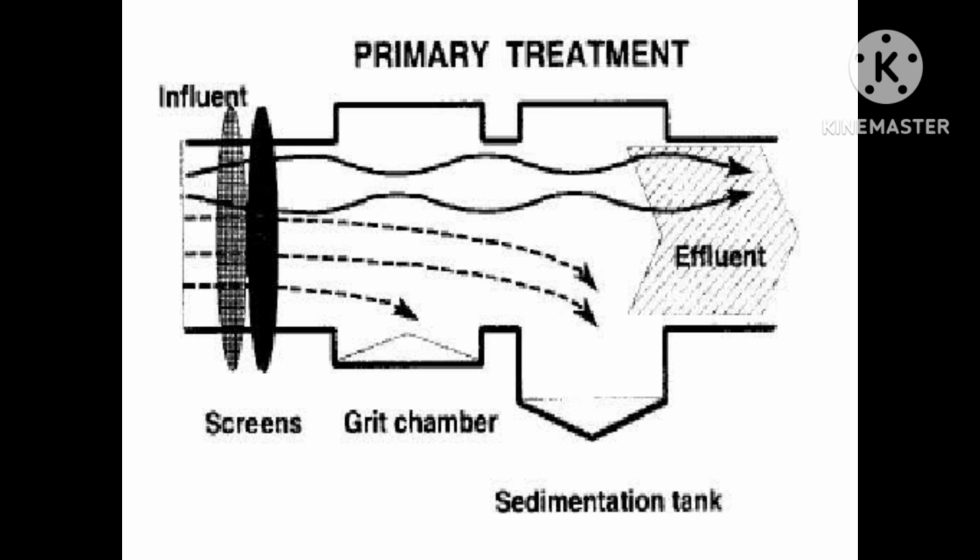Here the important point is that after the mixing process is over or completed, the effluent is sent to a sedimentation tank where sludge is deposited and water free from organic matter is drawn off. And to repeat the process, a part of the settled sludge is sent back for seeding a fresh batch of sewage.